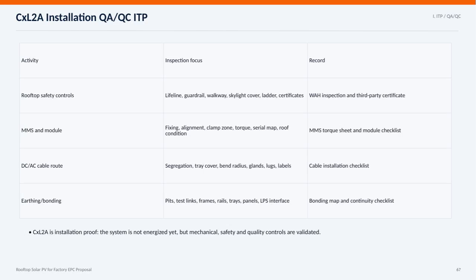Here, we focus on the installation quality assurance and quality control, or QA/QC, for the rooftop solar PV system proposed for the factory. The key activities cover several critical areas. First, rooftop safety controls include checking lifelines, guardrails, walkways, skylight covers, ladders, and verifying certificates, all documented through work-at-height inspections and third-party certificates. Next, for the MMS and module installation, we inspect fixing, alignment, clamp zones, torque, serial mapping, and roof conditions, with records kept in torque sheets and module checklists.